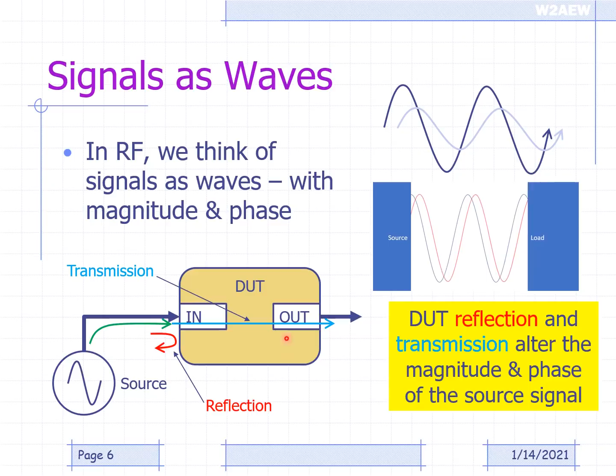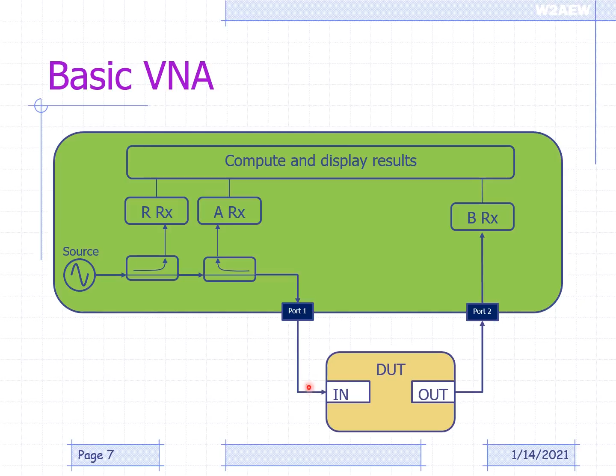So here's a basic VNA, this green block right here. We have a source that provides an RF signal that goes out through port 1 to a DUT port, and then any signal going through that port goes into port 2, and then any signal being reflected off of that port comes back this way. There are a set of directional couplers, or sometimes a bridge, that will measure and pick off a piece of the signal that's being sent out, that's our reference, as well as the signal that might be coming or being reflected back, and that's called our A receiver.